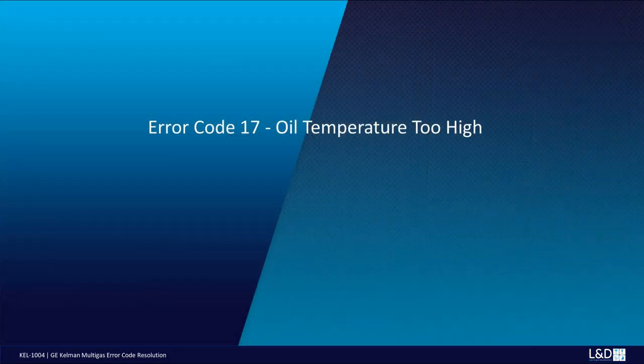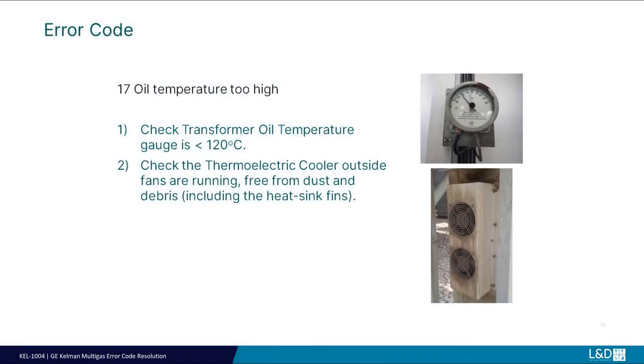Error code 17: Oil temperature too high. Check the transformer oil temperature gauge is less than 120 degrees Celsius. Check the monitor thermoelectric cooler outside fans are running, they are free from dust and debris including the heat sink fins. Check all other monitor air filters for cleanliness and good airflow.